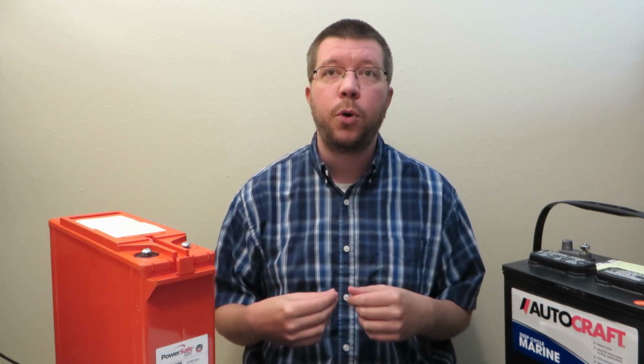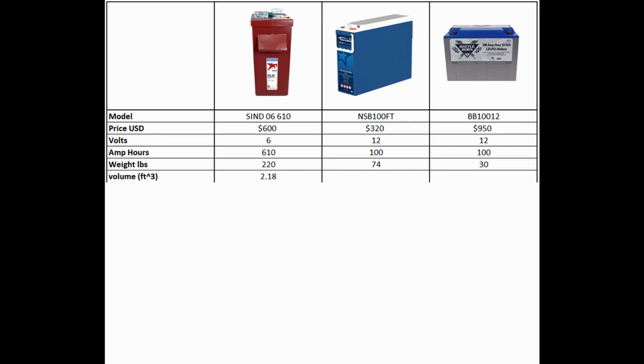In terms of battery size, we are going to go by battery volume. Floor space in a building or compartment space in a vehicle is usually what matters, but to keep things generic, we're just going to go with simple volume. The Trojan flooded battery is 15.33 inches by 10.22 by 24.01 tall, for a total volume of 2.18 cubic feet. The Northstar AGM battery is 15.6 inches by 4.2 by 11.3 inches tall, for a total volume of 0.43 cubic feet. The Battleborn battery is 12.75 by 6.875 by 9 inches tall, for a volume of 0.46 cubic feet.